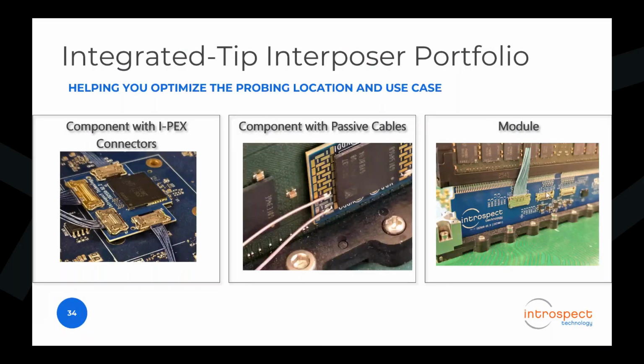And also, of course, the probing is still using the integrated tip interposer. So there's really just a high impedance tap coming into this microcoax cable. So the signal integrity in terms of reflections, especially from write side commands, let's say from the CA and the DQ from the PHY side driving into the memory, is generally very, very clean. But this is what we're using for high-speed debugging for both the RCD or for a complete RDIMM or MRDIMM.